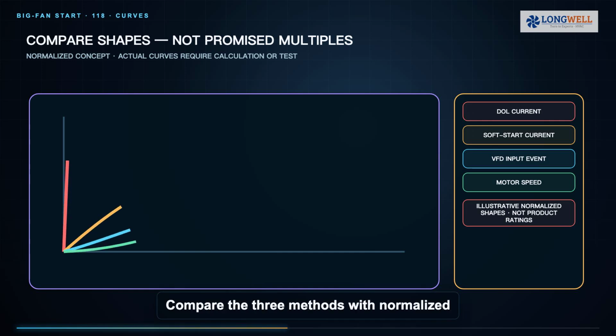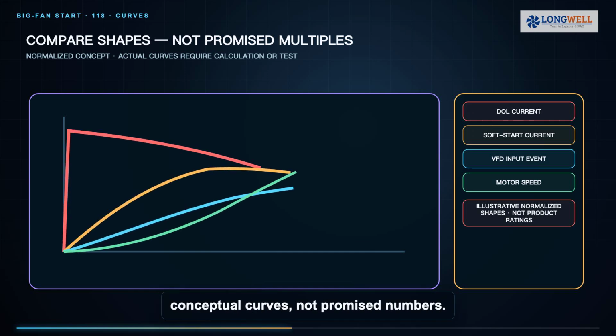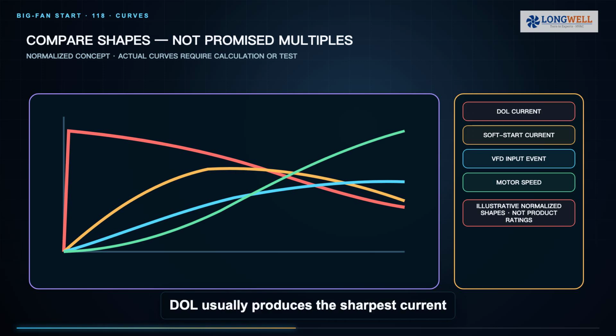Compare the three methods with normalized conceptual curves, not promised numbers. DOL usually produces the sharpest current step in the shortest event. A soft starter shapes the voltage and current ramp but still accelerates toward line frequency. A VFD shapes frequency, voltage, and speed together. The real curves must be calculated or measured for the chosen motor, fan, network, and settings.